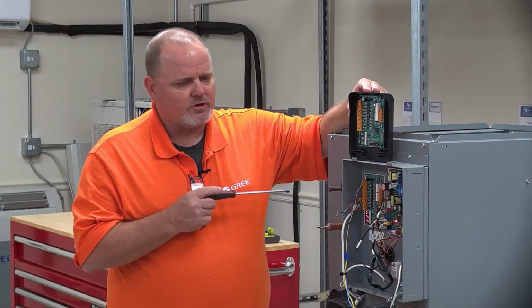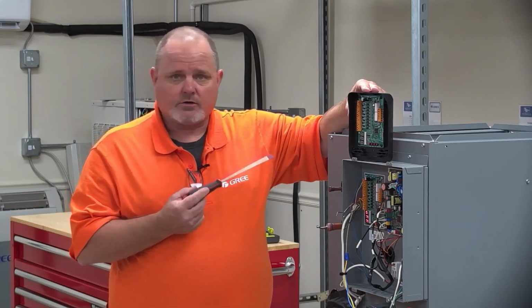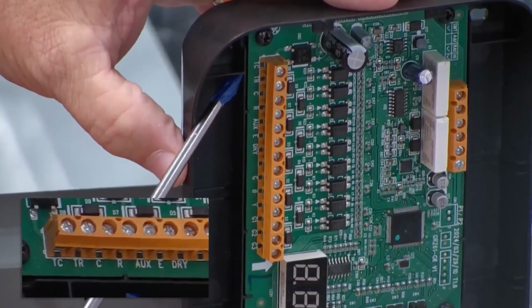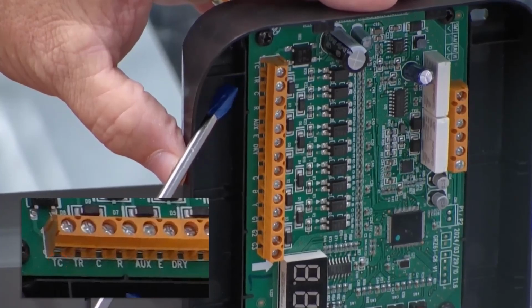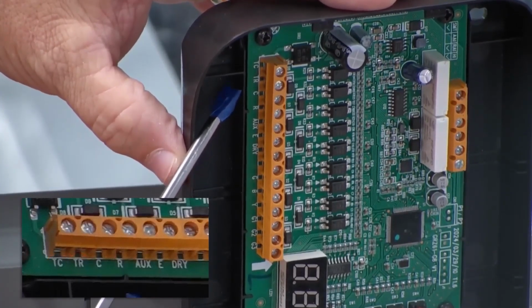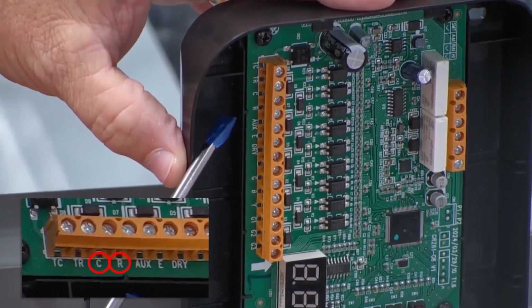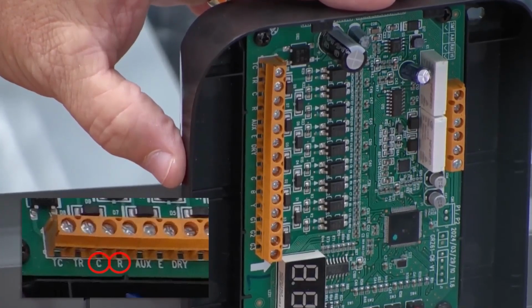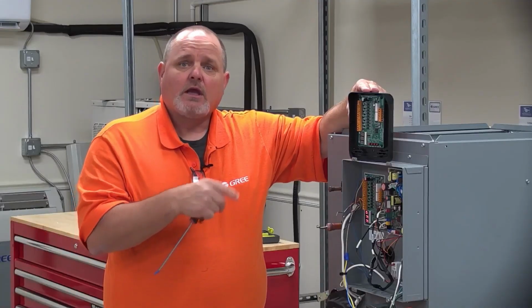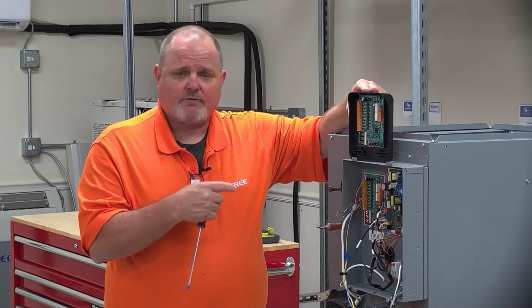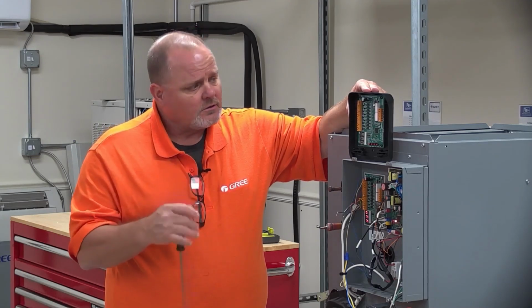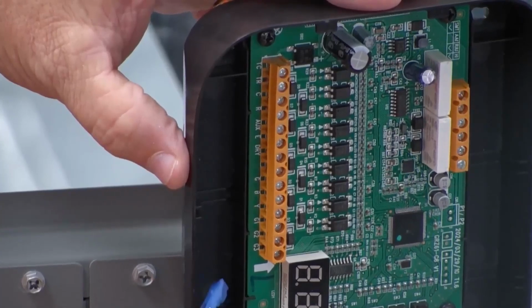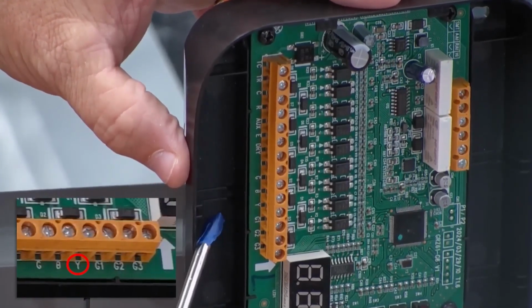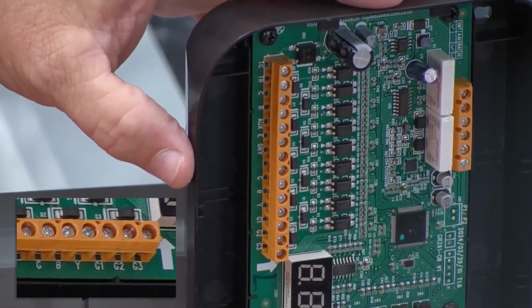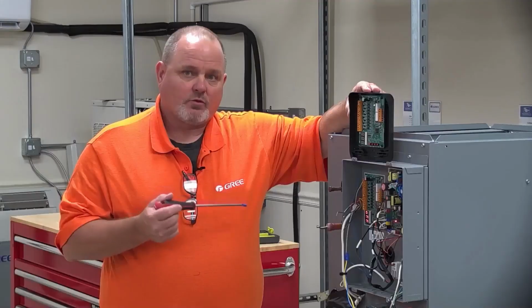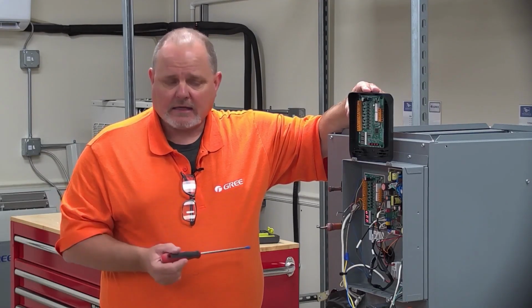So coming from your furnace, your 24-volt power, your R and your C, you will have to run that up here to TC. That'll be your common from your furnace, and your TR would be your R from your furnace. Then your C and your R here would be going to your thermostat connections, so you'd have 24-volt power to your thermostat at all times, and also give you the R that you need at your thermostat for your switching mechanism to turn different things on. The only other thing you're going to hook up on this board is Y, and we now have a B terminal, so that energizes the reversing valve. Remember, the reversing valve on GREE equipment is energized in the heating mode, not in the cooling mode.